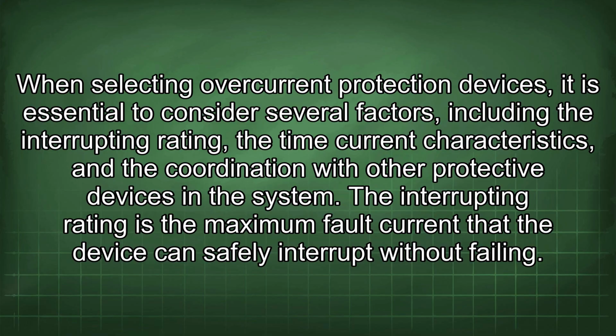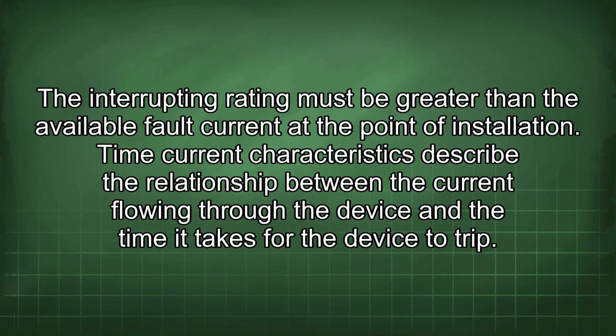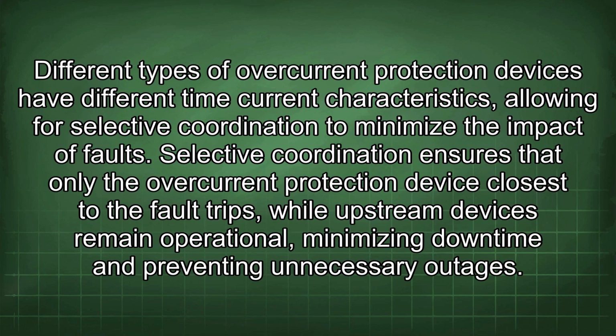The interrupting rating is the maximum fault current that the device can safely interrupt without failing. The interrupting rating must be greater than the available fault current at the point of installation. Time current characteristics describe the relationship between the current flowing through the device and the time it takes for the device to trip.